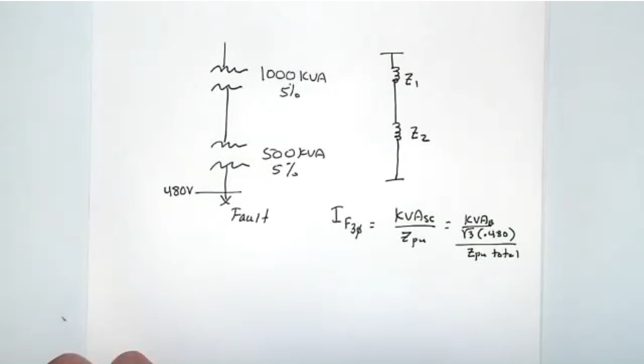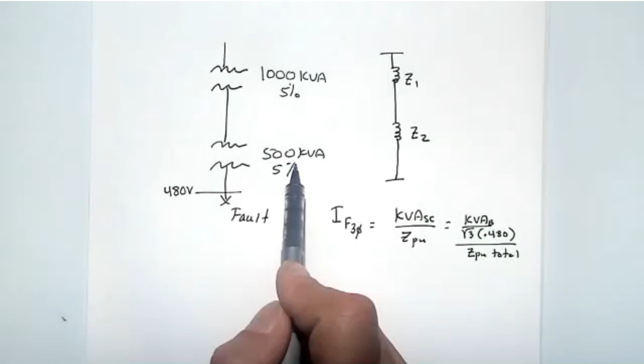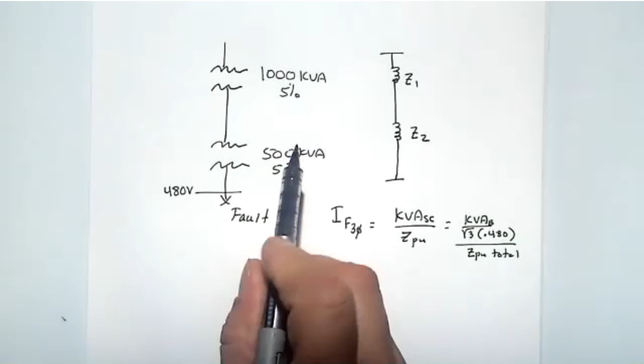Now, the nice thing is if we calculate the fault current here, the only thing we need to know is which kVA to use. We're going to use a kVA base, one or the other of those kVAs, and then we're going to use a Z per unit total, which is the series sum of those impedances. But we can't just take 5%, 5%, and call it 10%. We have to combine those on a common base. If you take this transformer and this transformer and ask which one delivers more fault current, I would say the 1000 kVA delivers more fault current. So if I put those side by side, the 500 kVA has a higher actual impedance in ohms compared to this one.